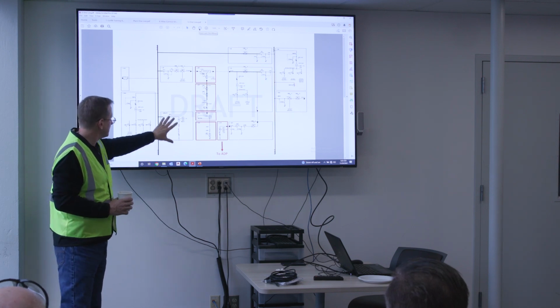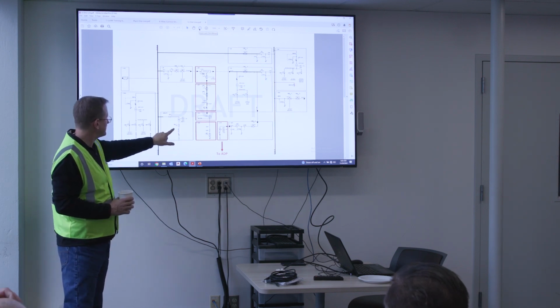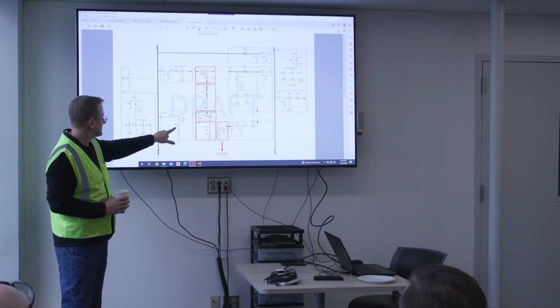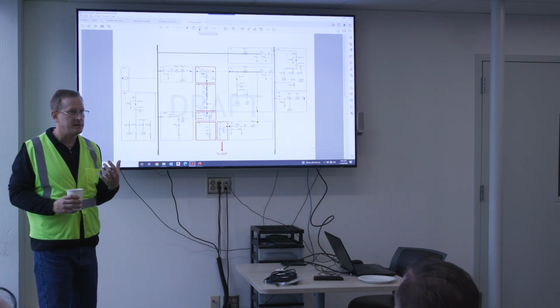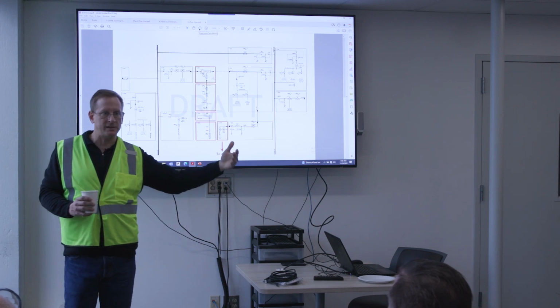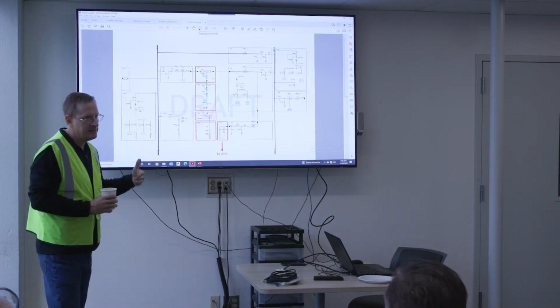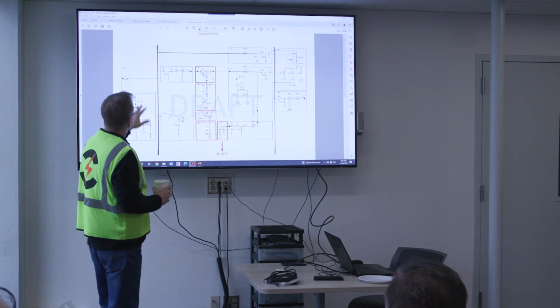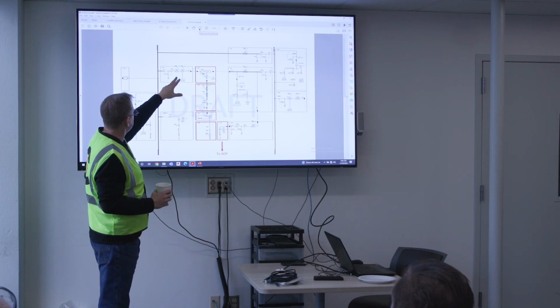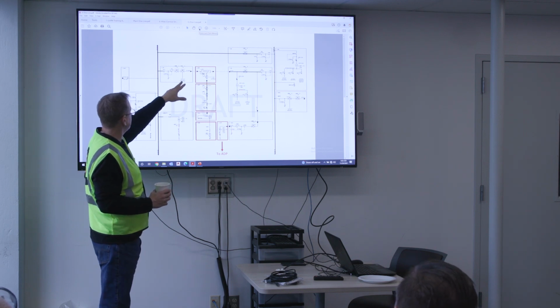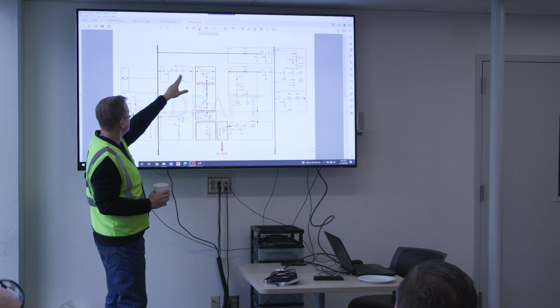So we take some of that power from this side off of this small transformer, which is built into the switchgear. It's in that first section on the left side: that 45 kVA transformer. I mentioned the Q1 breaker. You can see the CTs that we've got there, both for monitoring and for protection.